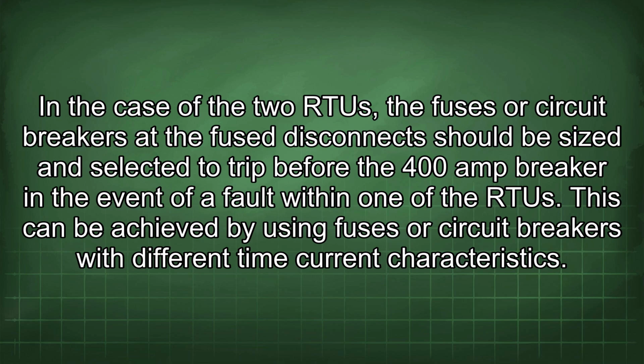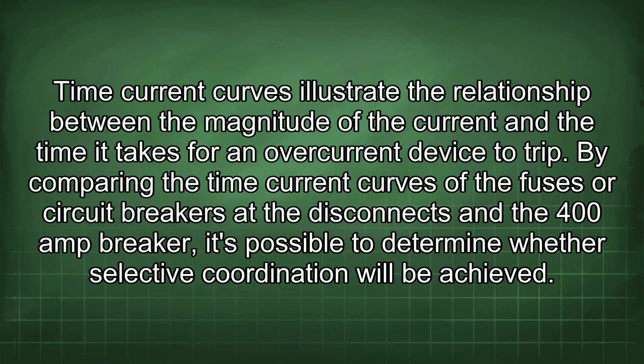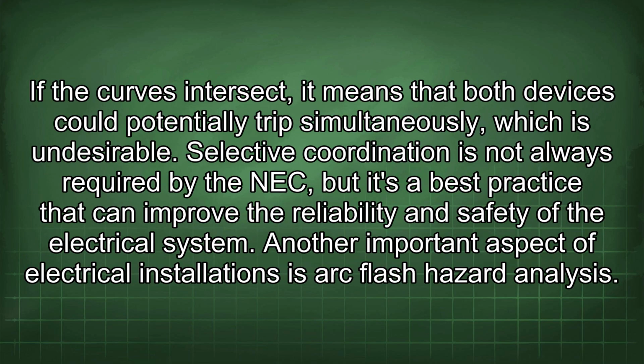This can be achieved by using fuses or circuit breakers with different time current characteristics. Time current curves illustrate the relationship between the magnitude of the current and the time it takes for an overcurrent device to trip. By comparing the time current curves of the fuses or circuit breakers at the disconnects and the 400 amp breaker, it's possible to determine whether selective coordination will be achieved. If the curves intersect, it means that both devices could potentially trip simultaneously, which is undesirable.